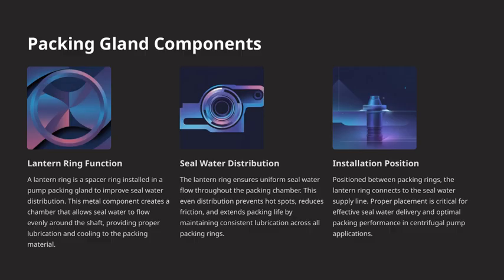Finally, the placement of the lantern ring is key. It is positioned between the packing rings and connects directly to the seal water supply line. Proper installation and placement are critical because they ensure effective seal water delivery. When everything is correctly positioned, it leads to optimal packing performance, especially in centrifugal pump applications. Overall, understanding these components and their functions helps us maintain efficient and reliable pump operations.